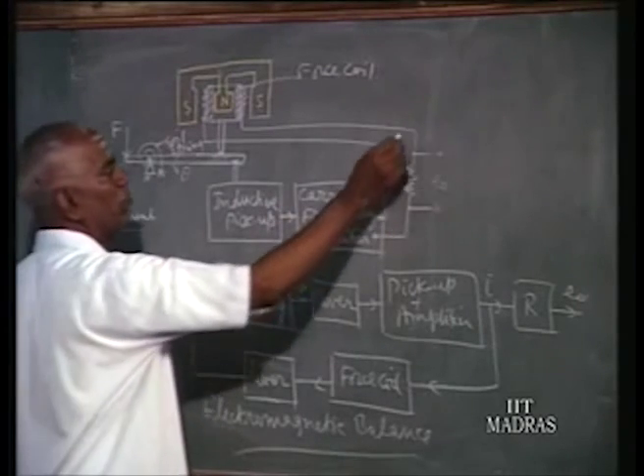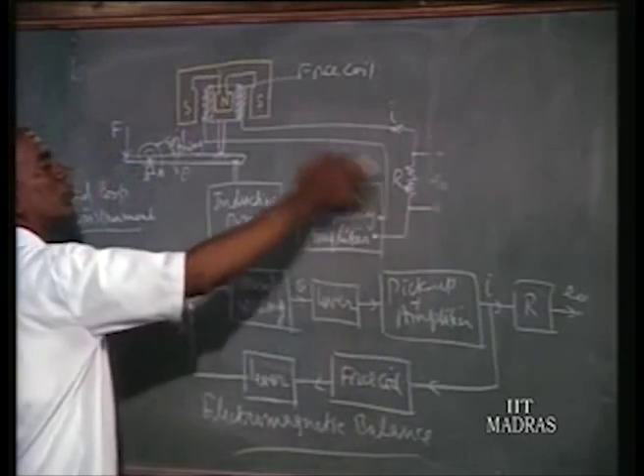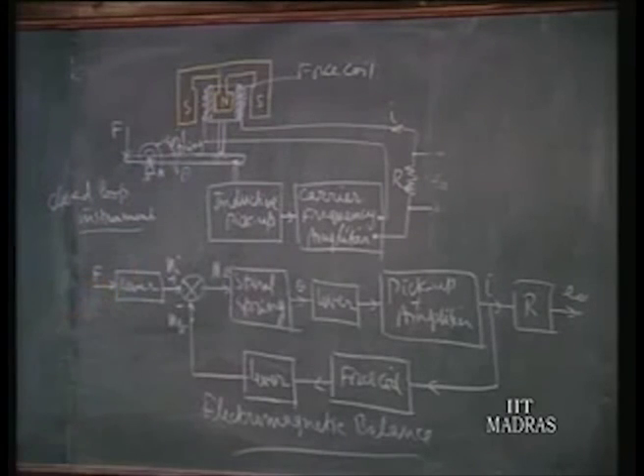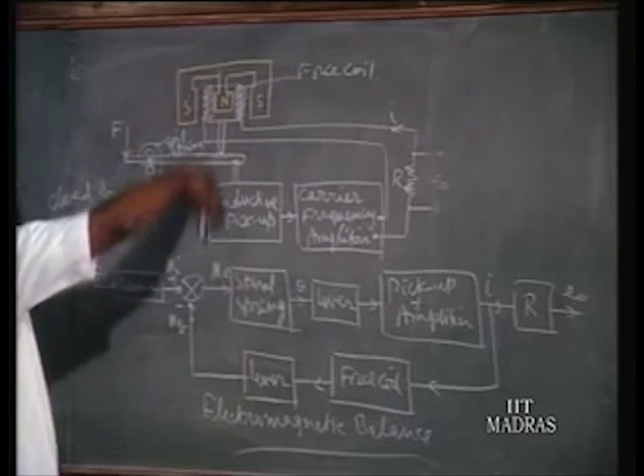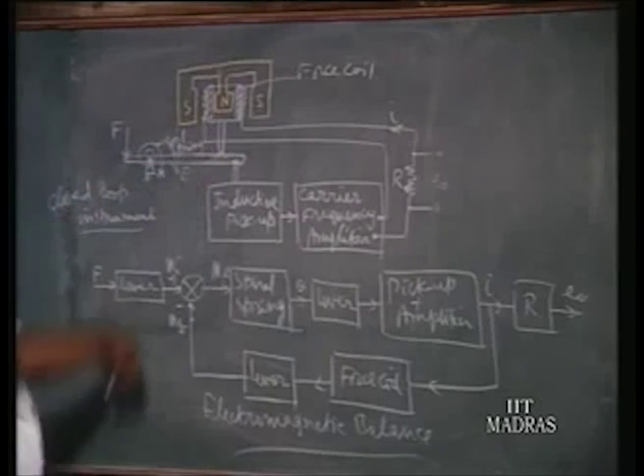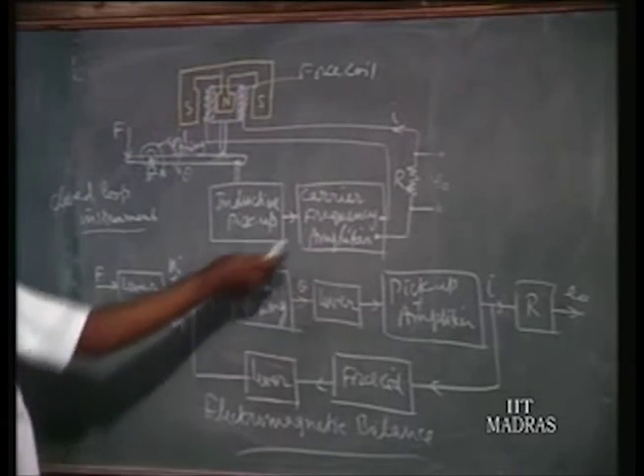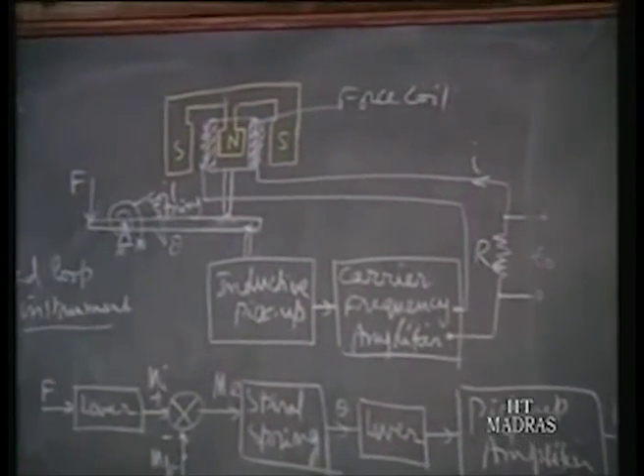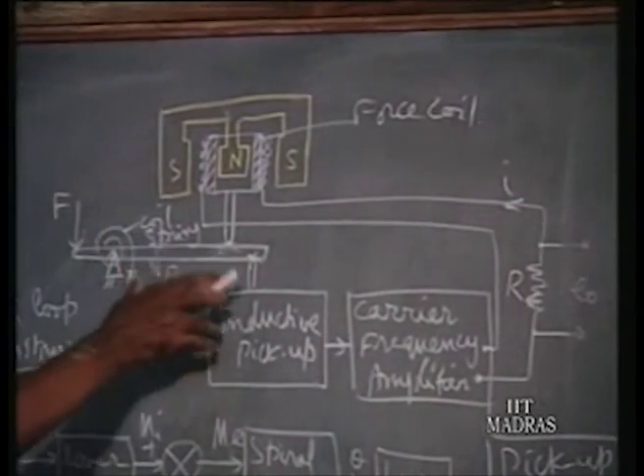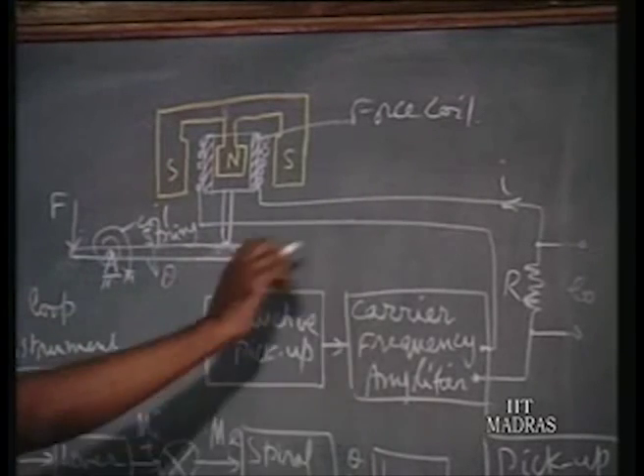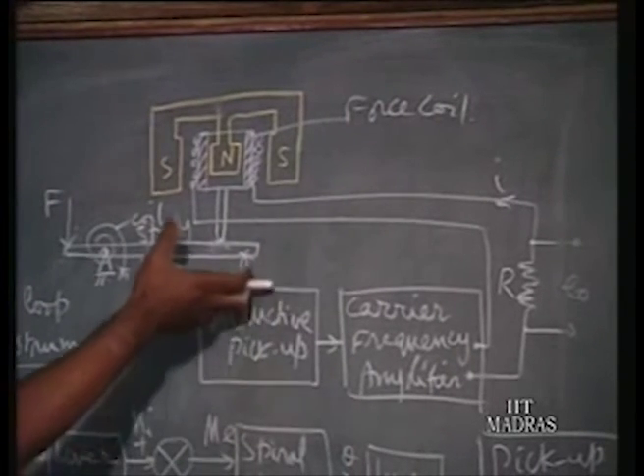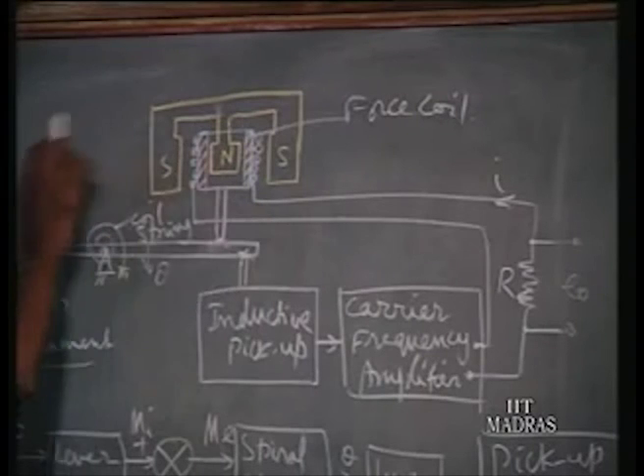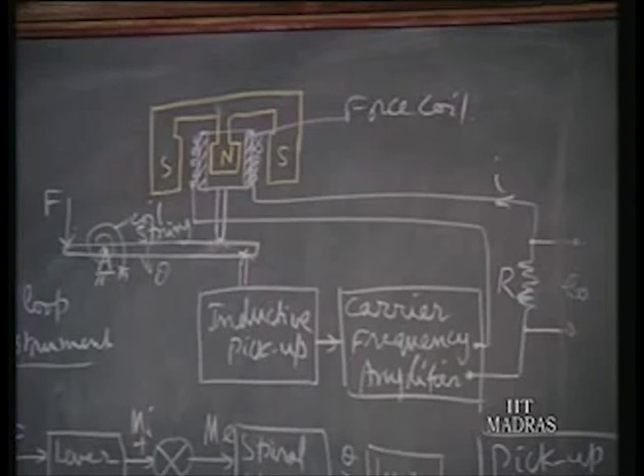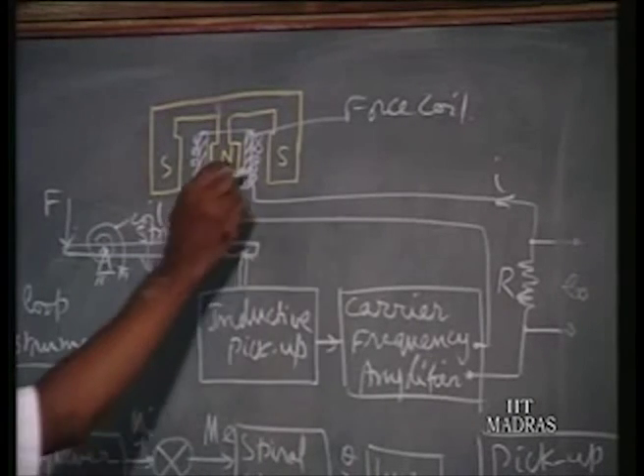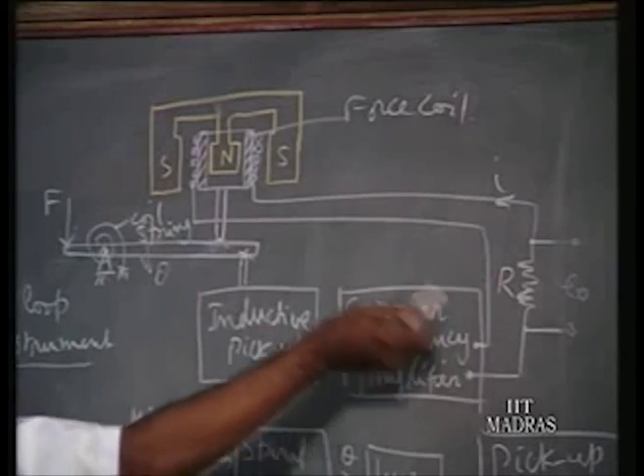That displacement is given to the carrier frequency amplifier. The current I flows, and this current is taken to the force coil. The force coil gives rise to a force bringing the lever back to its original position. So the amount of current required to bring it back is a measure of the force. If the force is larger, it will tilt more and a higher current will flow. The force required in the coil to bring the lever back is proportional to the current flowing in this system.